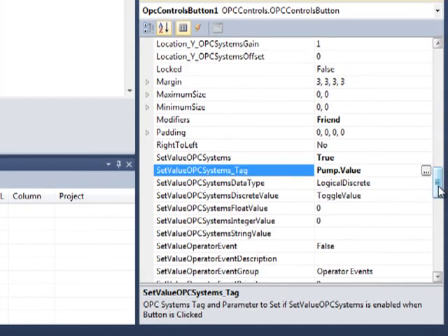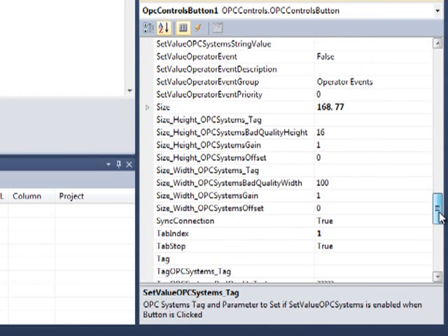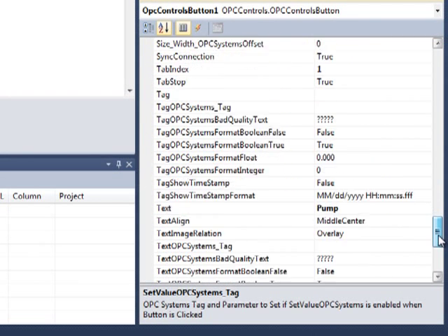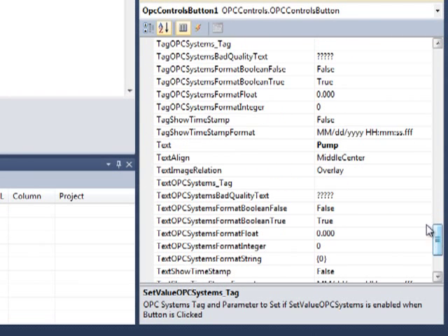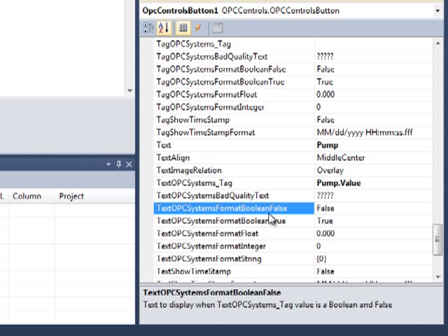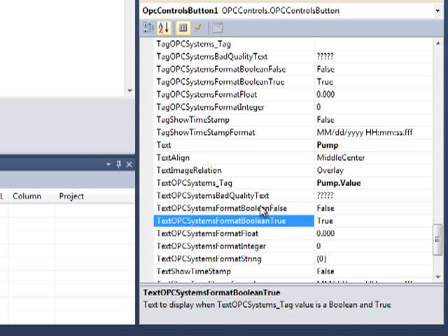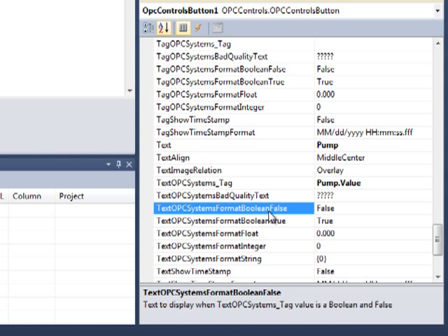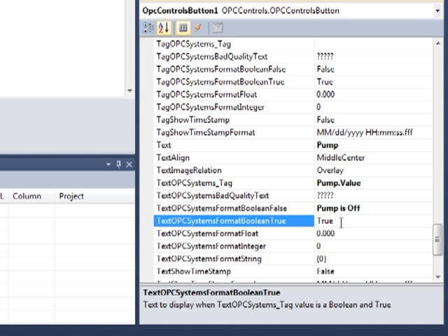Now let's scroll down and select the text property. Under text OPC Systems tag, I'm now going to paste that same value in there. Now let's look at the boolean false and boolean true properties. That's what would be displayed for our text on the button. So let's change that. Let's change the boolean false to pump is off and let's change the boolean true to pump is on.